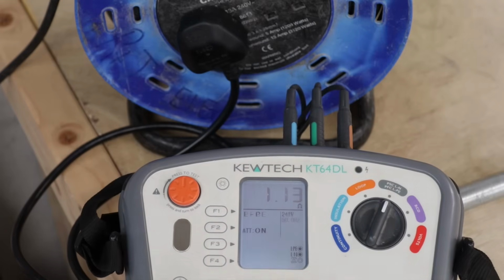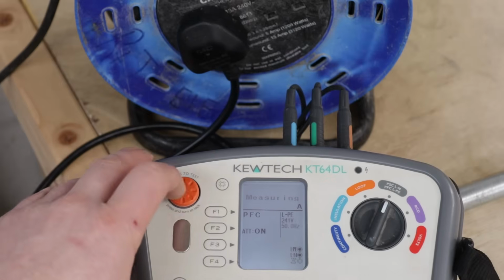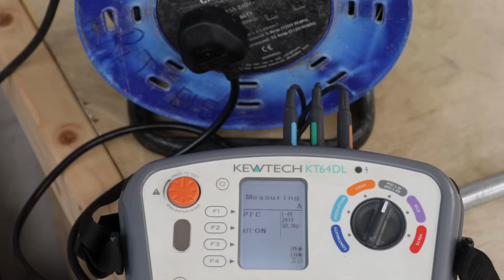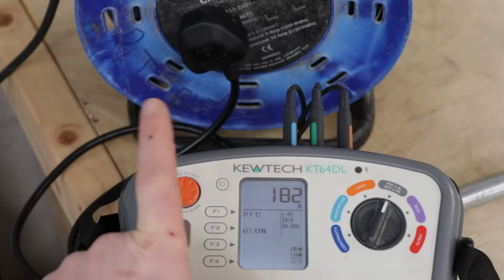Now, if I go to my short circuit current, let's see what we get now. So it's now down to 182 amps. So I've halved it. So you can see I'm getting very close to the point where that breaker is not going to trip. And I've oversized my socket cables and my mains cable to keep this down. So you can see the danger of an extension lead.